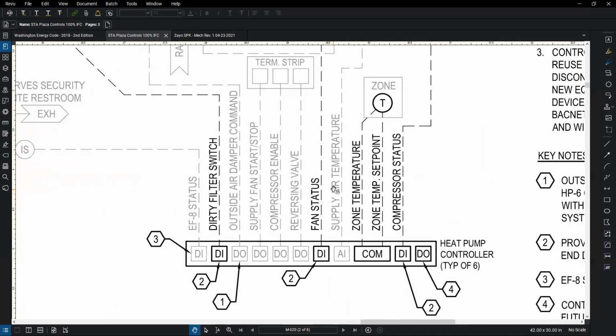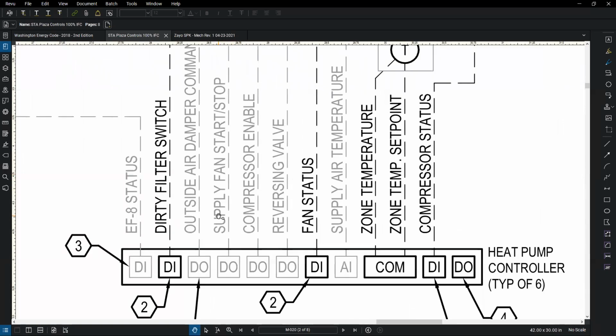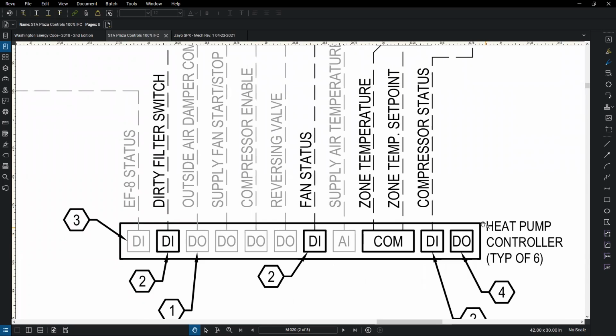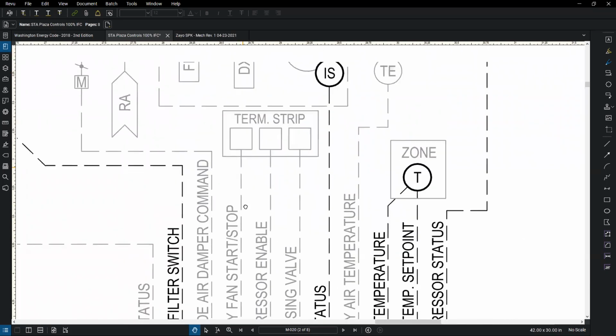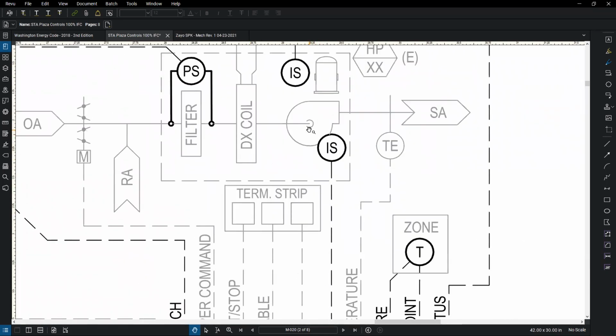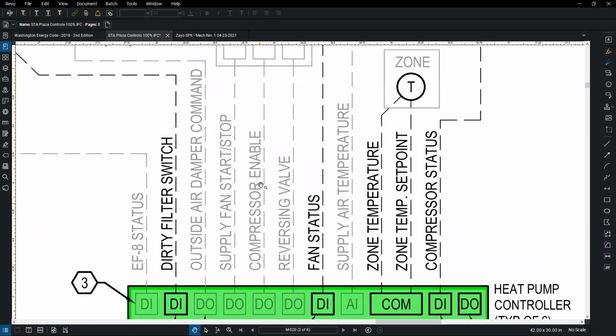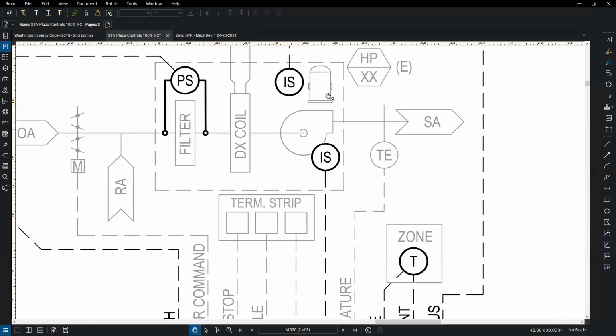And then you have to turn your head 90 degrees to read this, but these are all the control points. So for example, this supply fan start stop. This is a digital output. This is a binary signal from the DDC controller, which is represented by this box. So this will send a signal out to the unit to tell this fan to run. Then we have the compressor enable. Similarly, send a signal out to the unit, tell the compressor to turn on. So this is how we're controlling this equipment.